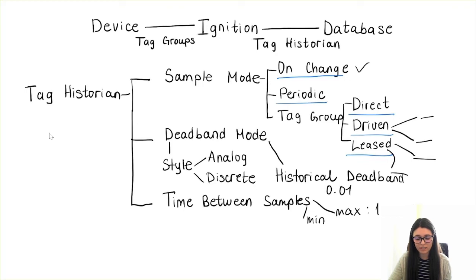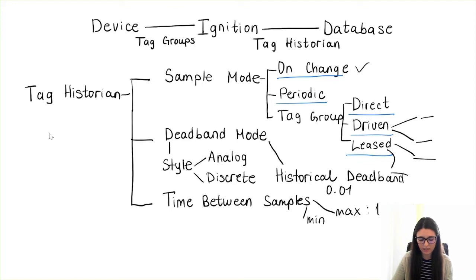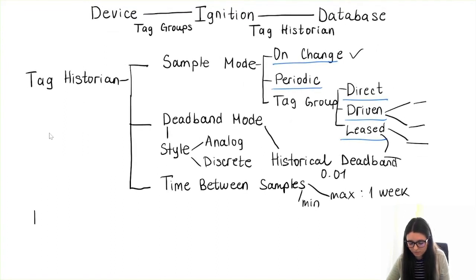So those are the three main settings in the tag historian: sample mode, deadband mode, and time between samples. As mentioned at the beginning, we want to store data in a format that leads to an optimized structure — fast access, efficient SQL queries, and good organization. We don't want to keep all historical data in a single table, as that would lead to enormous amounts of data in a short time. Once we've configured the tag historian settings, we can look at data partitioning and data pruning.